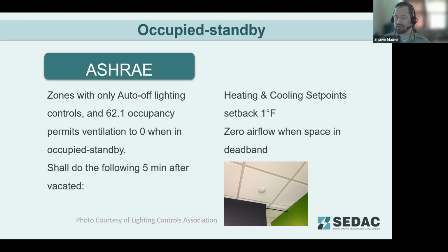As we noted in some of our previous presentations, the typical minimum deadband that's mandatory in the IECC and ASHRAE is a 5-degree deadband between the heating and cooling set points. So with this control setting, it increases that deadband 1 more degree. So you've got a total of 6-degree deadband. And while a 1 degree difference may not make a substantial difference in comfort for the space, it does allow that system airflow to be decreased for a longer period of time, which gives you more savings on the fan energy. And so it's a nice addition that ASHRAE has for accounting for variable occupancy in buildings.